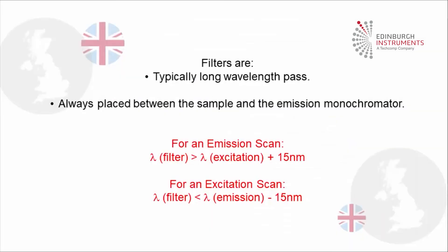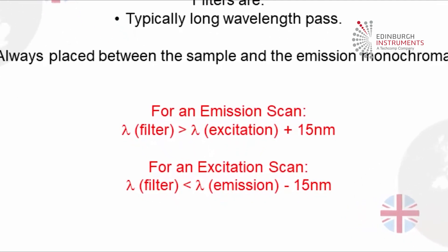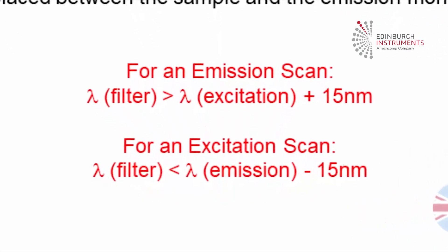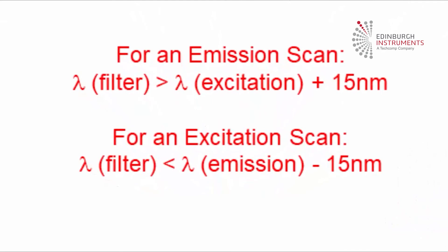The stationary monochromator in each scan defines the wavelength of the filter. For an emission scan, the filter wavelength should be greater than the excitation wavelength plus 15 nanometers. For an excitation scan, the filter wavelength should be less than the emission wavelength minus 15 nanometers. The filter is normally placed between the sample and the emission monochromator.